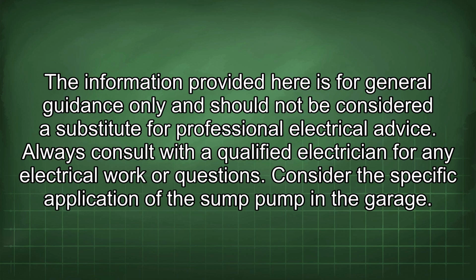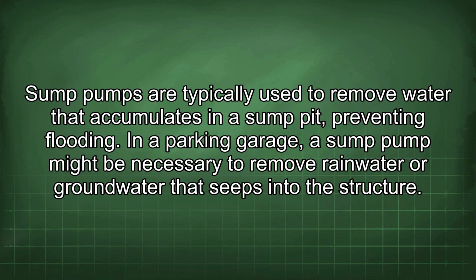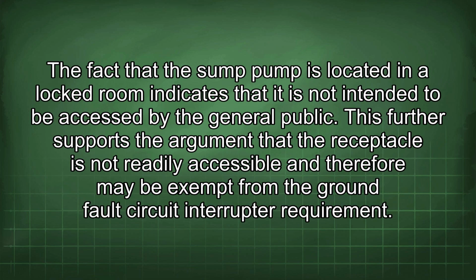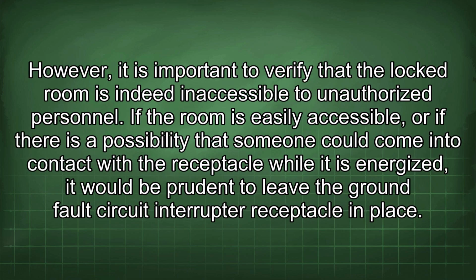Consider the specific application of the sump pump in the garage. Sump pumps are typically used to remove water that accumulates in a sump pit, preventing flooding. In a parking garage, a sump pump might be necessary to remove rainwater or groundwater that seeped into the structure. The fact that the sump pump is located in a locked room indicates that it is not intended to be accessed by the general public. This further supports the argument that the receptacle is not readily accessible and therefore may be exempt from the ground fault circuit interrupter requirement. However, it is important to verify that the locked room is indeed inaccessible to unauthorized personnel.